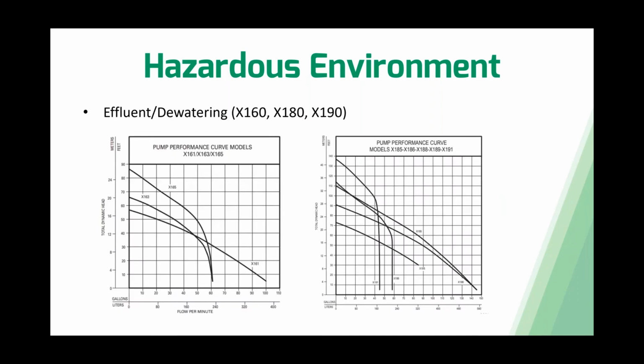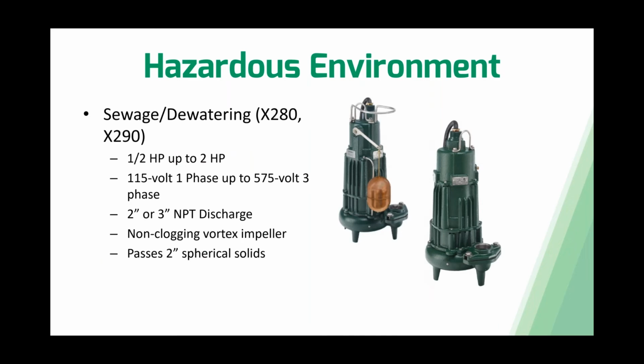So when it comes to the pump performance, I wanted to throw these up here just to give you an idea of the broad offering from the X160s up to the X190s. Within the 160 series, you have the pumps that can go out to 100 gallons per minute on the X161. Or on the X165, if you need a little bit lower flow than that, but you need higher heads, the X165 can get up almost to 90 foot of total head. And then for the X180s and X190s, when you're looking at the gallons per minute, it gets a little bit over 140 gallons per minute down there at 5 and 10 foot of head. And then for a higher head, super high head for the X190 series, these pumps go over 130 foot of total dynamic head. Within the sewage, now the sewage and dewatering, which is the X280 and X290, and then a couple others which we'll touch here in just a minute.